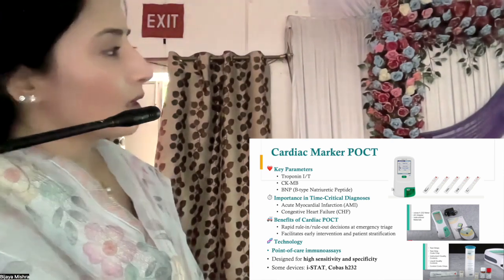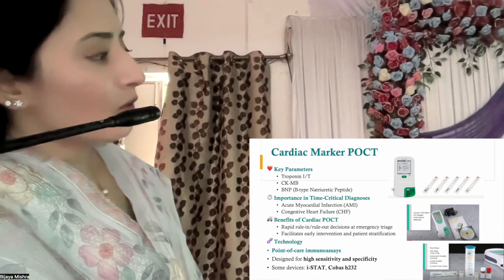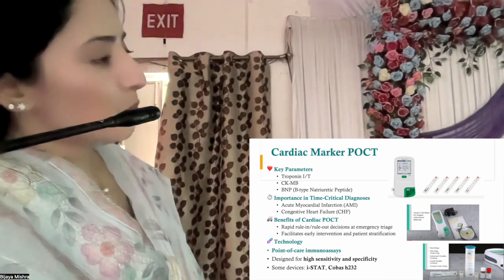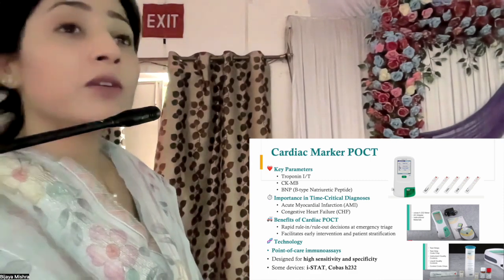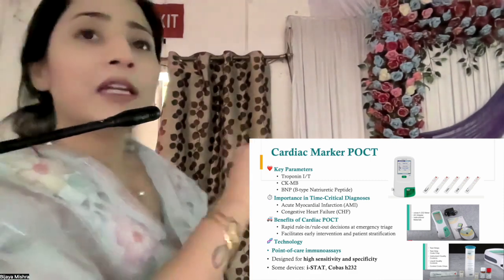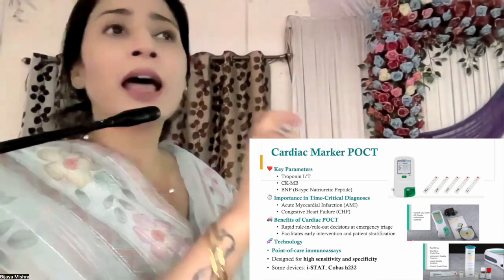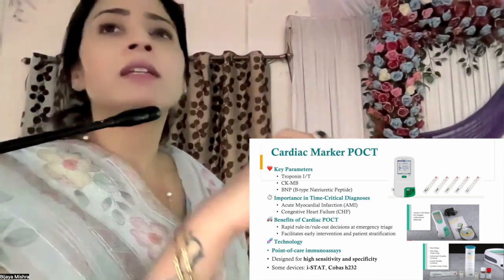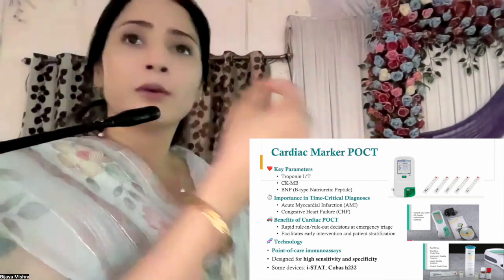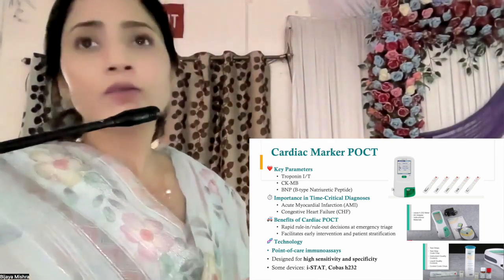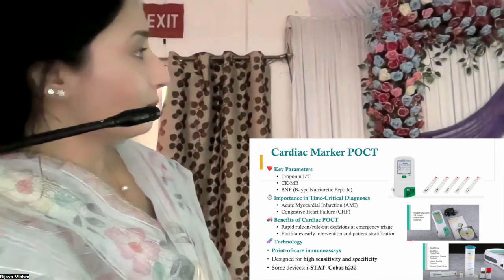Here, all I want to show is this device that we saw earlier. Here we have the manufacturer leaflet with the CD, which provides all the details about the instrument. One thing that I want to highlight here is the quality control sample. Many of the quantitative devices that we use for POCT have a quality control sample provided. So we need to be very careful to use this QC run every time we are testing a patient sample, depending upon the patient load.